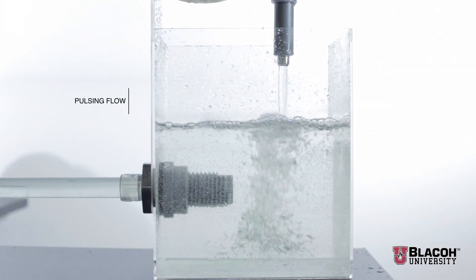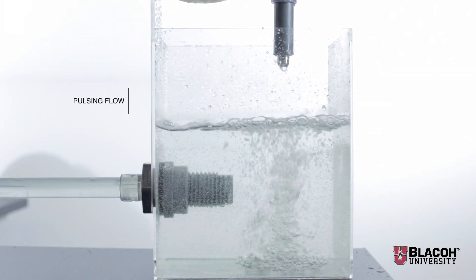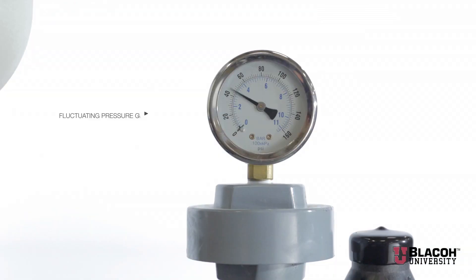There is a very large swing in pressure on the pressure gauge. The flow actually stops at every rotation of the roller shoe. As we activate the dampener by opening an isolation valve, you'll notice that instantly the flow becomes steady and smooth.